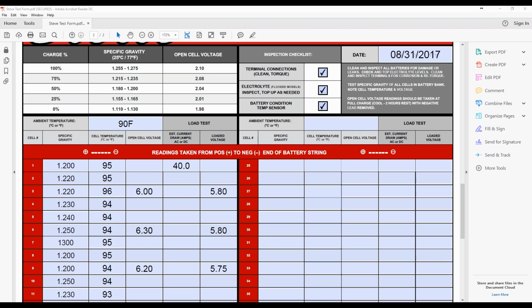If you have an industrial-based system where you're getting 8 to 10, 12 hours of charge a day, then a lower specific gravity is okay. But in a solar system, you're only charging 4 to 6 hours a day on average, and sometimes that's even worse. So one of the things you want to watch out for is to get your specific gravities a little bit higher, because you're not charging as long as an industrial application would charge.